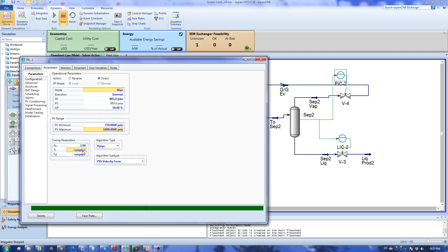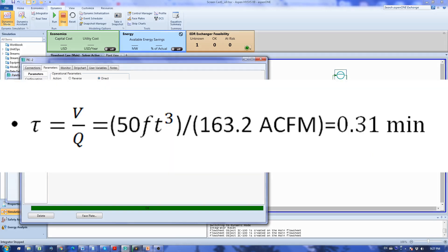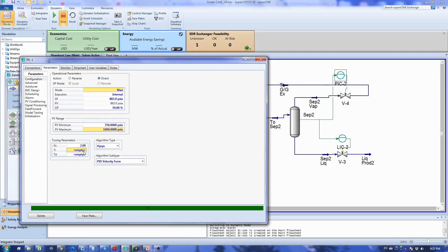For this we need to find the time constant of the process which is calculated by dividing the volume of the vessel, the gas part of the vessel, by the gas flow rate. I'm going to show the calculation in a bit but the process time constant came to 0.3 minutes.